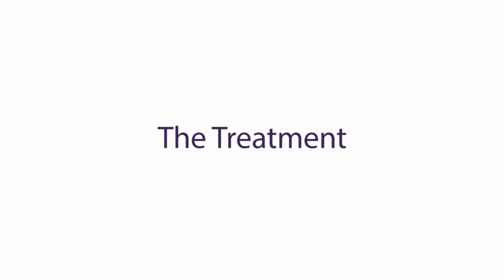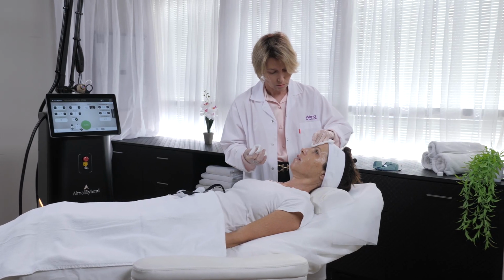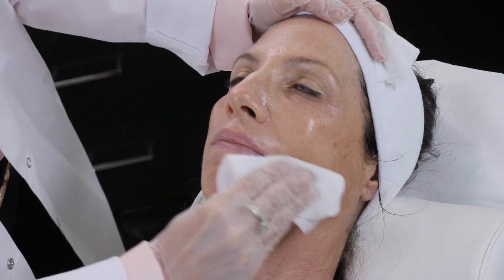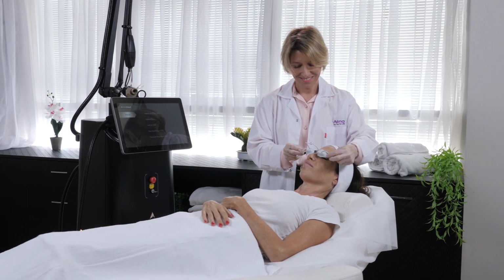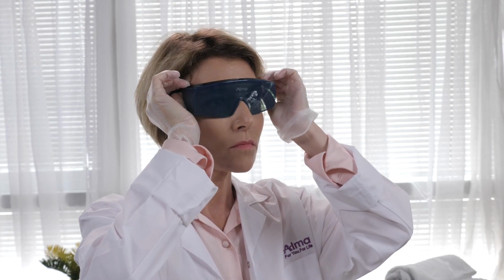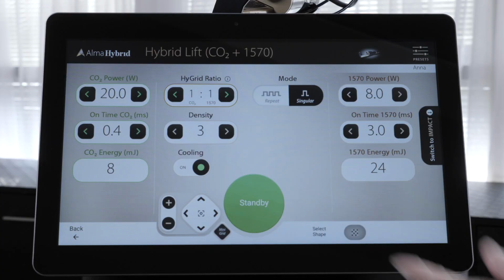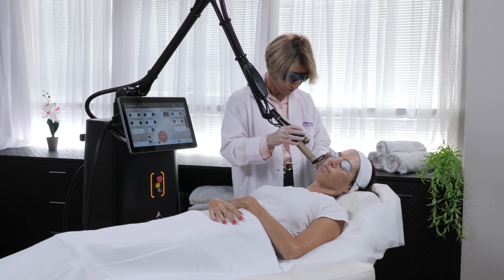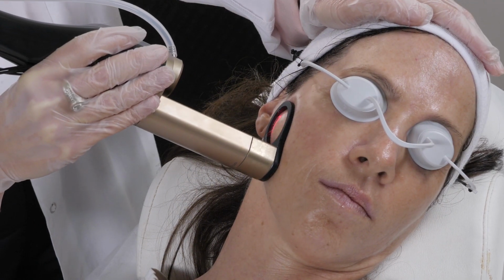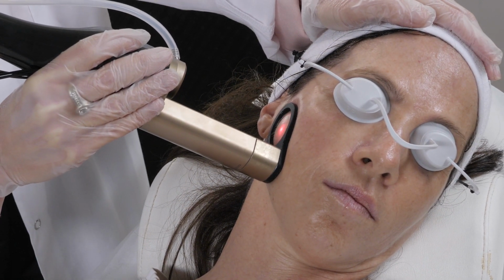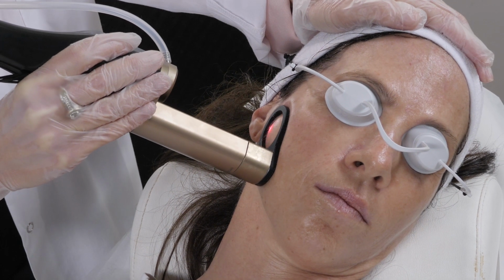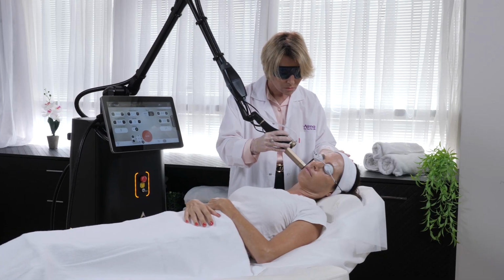The treatment. Clean patient's face from any makeup or numbing cream. Be sure to wear protective eye goggles or eye shields for treatment. Switch to Ready mode by pressing the Standby button in order to start the treatment. Place the applicator perpendicular to the skin and press on the foot switch to emit laser. Work in a stamping method.